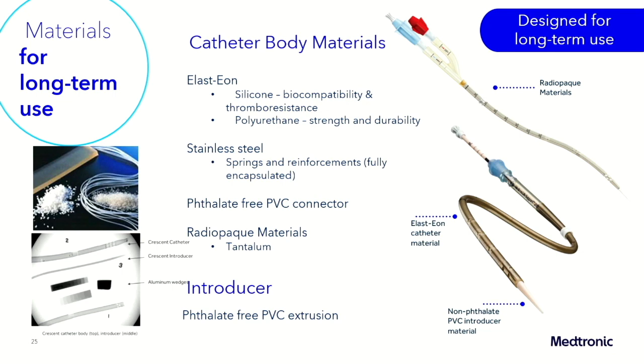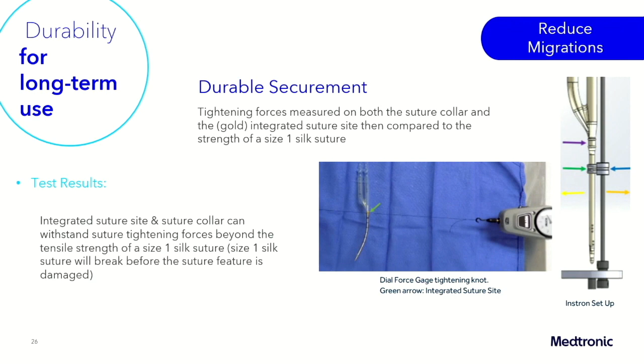Moving on to some things like durability testing. Again, this isn't exhaustive of all the testing, but just a general overview of what some of the testing looked like. So durability testing makes sure that the securement device doesn't move, right? If these cannulas are migrating or moving, or if they're cracking, that's not going to be good for our patients. And so we make sure they can withstand the test of time for each of your ECMO patients. Cannulas also went to lab testing, so testing these for 30-day long-term use for hemolysis, also testing them on the bench, flowing through them for 30 days, making sure that the biocompatibility testing is under this 30 days.